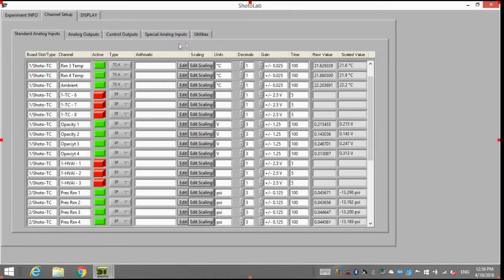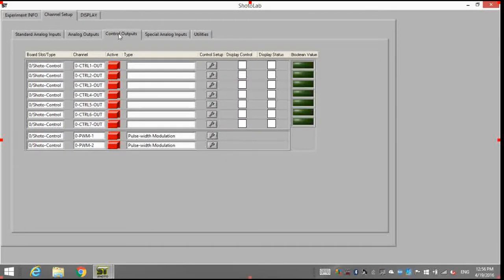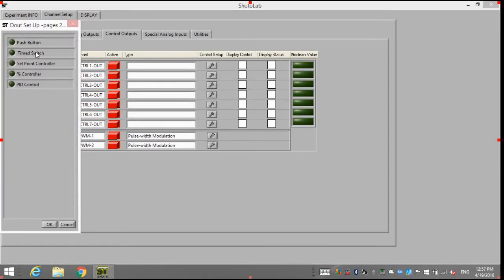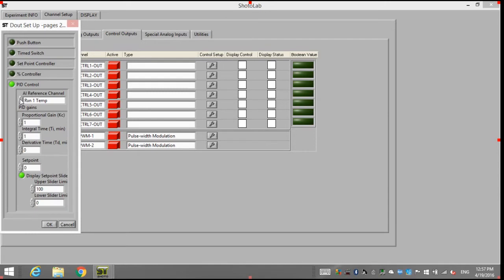Finally, you have to configure the PIDs. To do this, click on the Control Output tabs, click the wrench, and here you see all of the control options we have. These work in conjunction with the Shoto Lab power supplies. And in this reaction, we're going to be using the PIDs, so click that. For heating mantles and resistance heaters, experience has shown that 8 is a good P-value or proportional gain value. And 10 works for the integral value, so type those in. And keep 0 for the differential value.